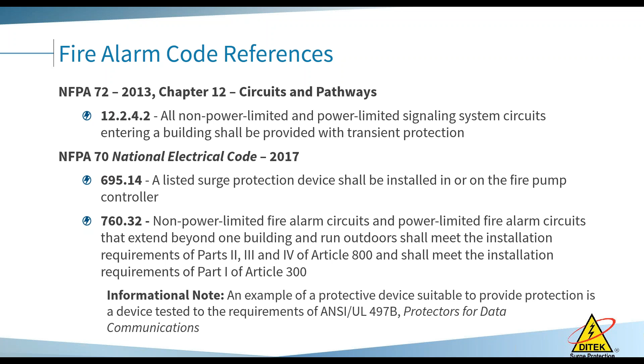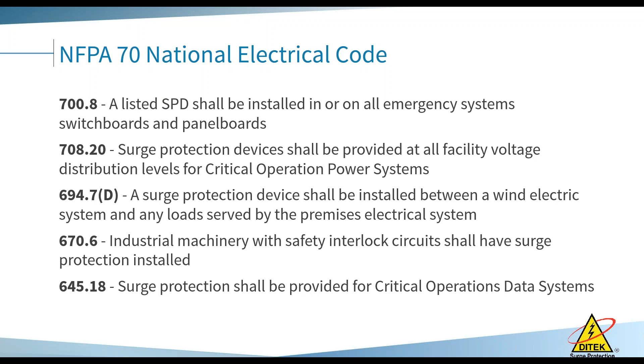NFPA 70, which is our National Electrical Code, obviously, on any emergency systems, SPDs are required now. It should also be required, provided at any facility low voltage distribution levels for critical operation systems. It should be installed in wind electric systems and any load served by that system. Industrial machinery with safety interlock circuits shall have surge protection. It shall also be provided for critical operations data systems. So a lot of these things have changed. In the past, a lot of these said should have surge protection, and now they say shall. I think safety being the issue.